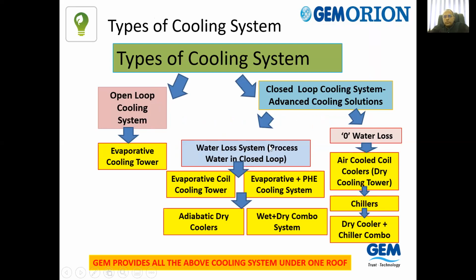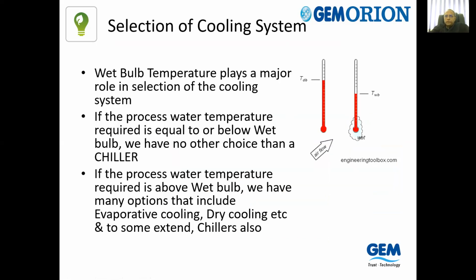One is to have a closed loop system with very little evaporation losses. And we can have a complete closed loop either by using a fully air-cooled system or by using a complete chiller for even low and high temperature application, or with a combination of both dry cooler as well as chiller. So these are all the possibilities for keeping systems in place where you want to save water, save the process, have reliability, and increase your cycle time also. So basically, the concept of cooling starts from the wet bulb temperature.